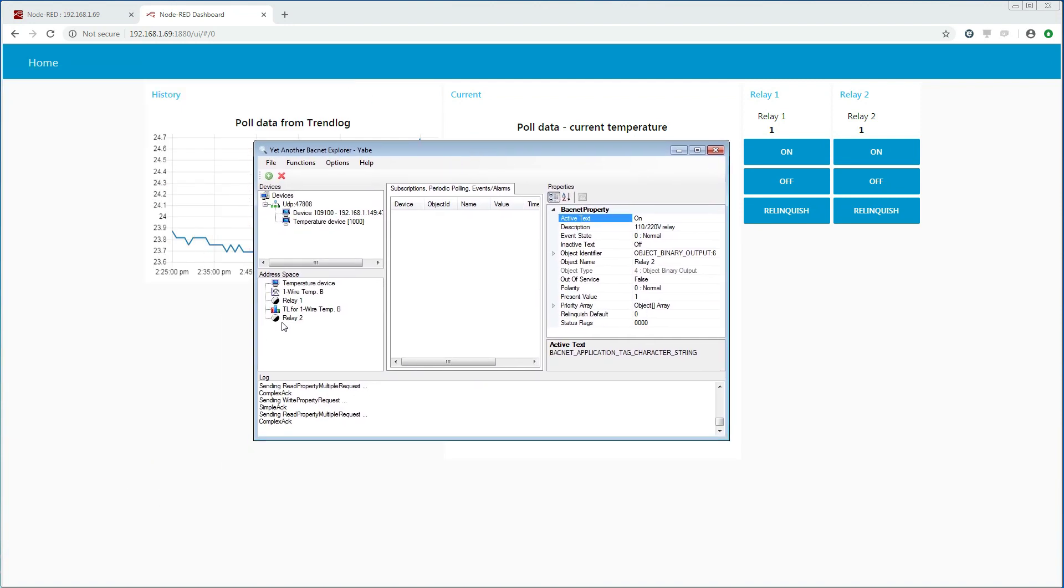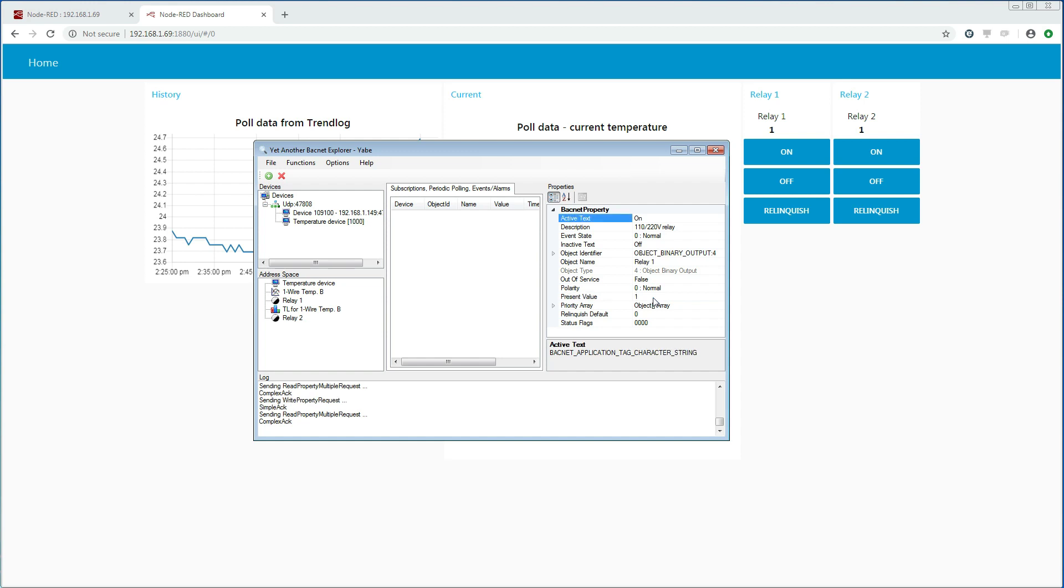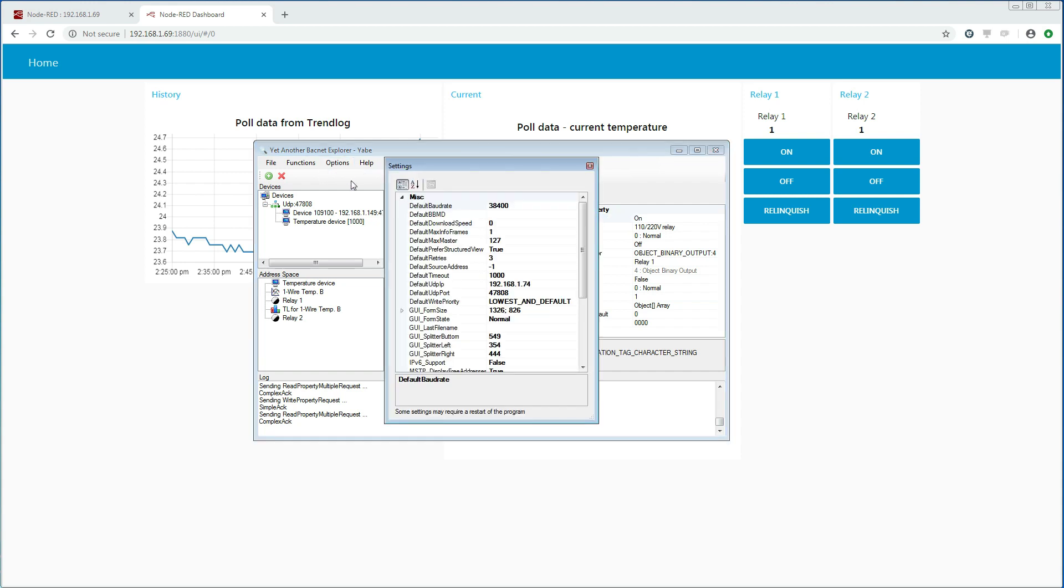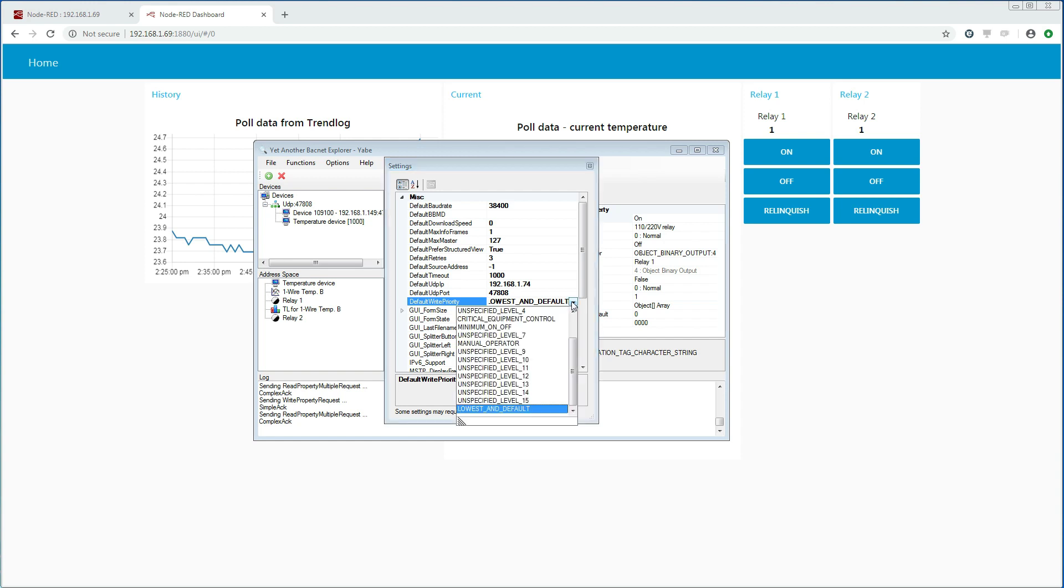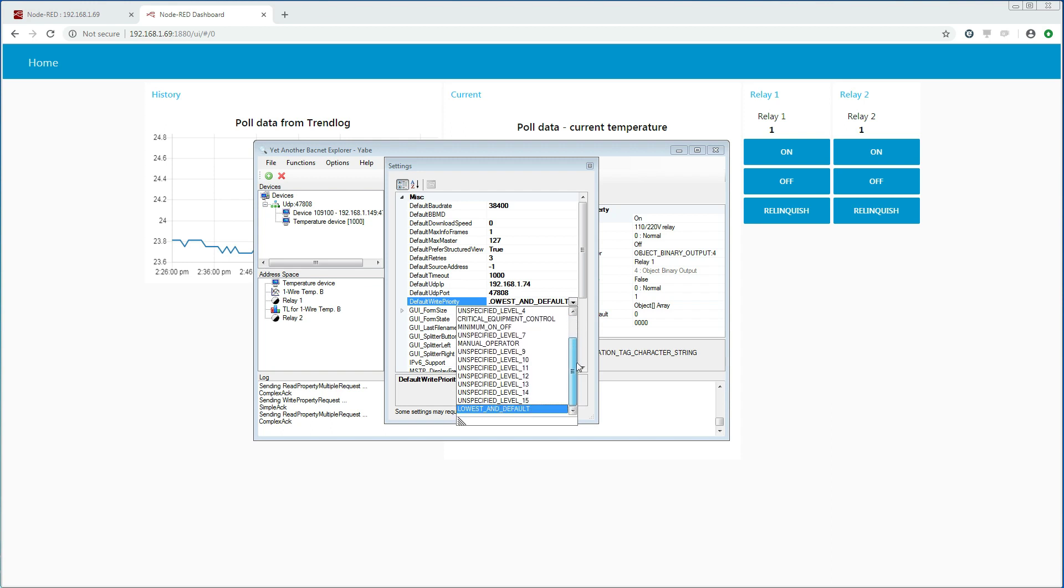Now let us go back to the BACnet explorer and try to turn relay 1 off. And we can see that it does not work. The reason for that can be seen when we look at the priority level that the BACnet explorer is using. We see that it is using the lowest priority level or level 16. We were using level 8 or manual operator. A lower number actually indicates a higher priority. So this means that the only way that the BACnet explorer can now write to the BACnet property is to use priority level 8 or higher. Another option is for us to relinquish the BACnet property that we have been writing to.